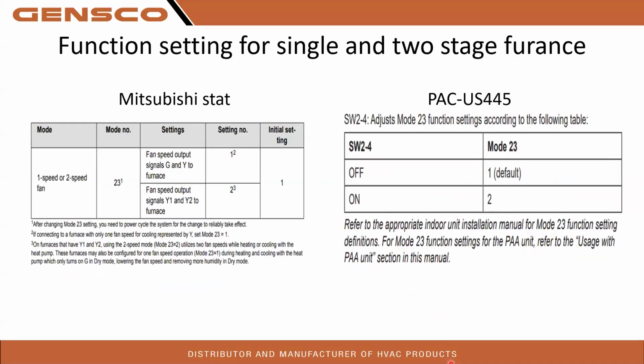Function settings for single stage and two stage furnace. You have to tell the IntelliHeat if it has a single stage or a two stage furnace. So again, if you're using a thermostat, MHK2 or PAR-40, it's going to be function setting 23. Setting 1 is going to be for your single stage. Setting 2 is for your two stage. On the PAC US 445 it is SW2 switch 4. Yes, the instructions on the 445 can be very confusing. Hopefully this is helping you out a bit.